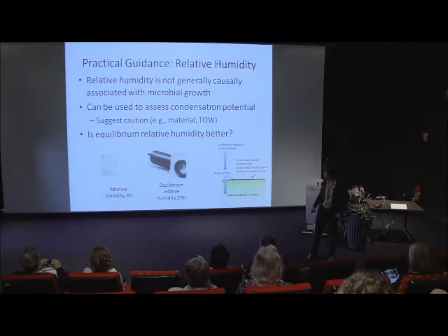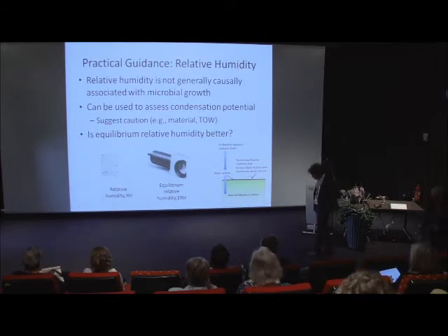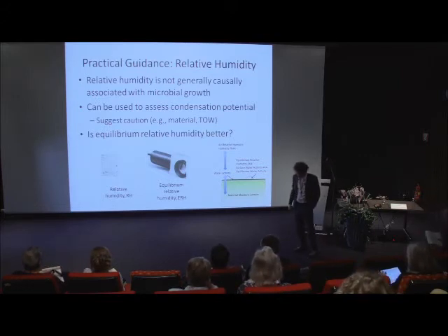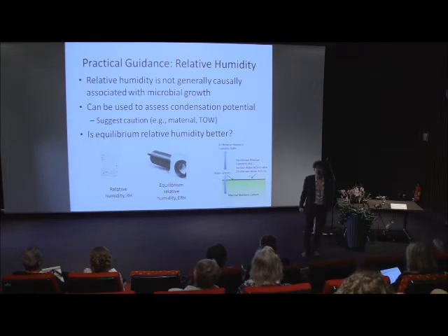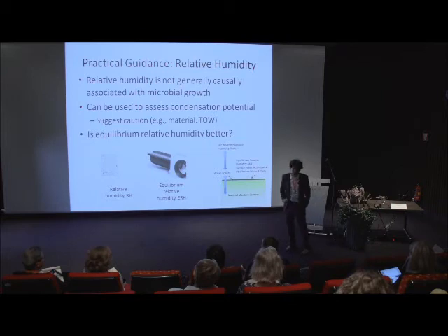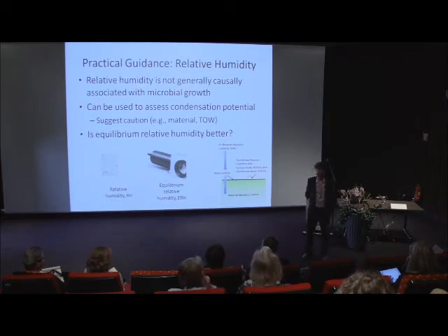So for example, when you measure relative humidity, if you see it go above 70% for many people, or 80% for some people, then you've got a problem and you fix your building design. But I'm going to suggest a lot of caution here, because a lot of materials in buildings can get wet and be just fine, especially if they're not wet for that long.